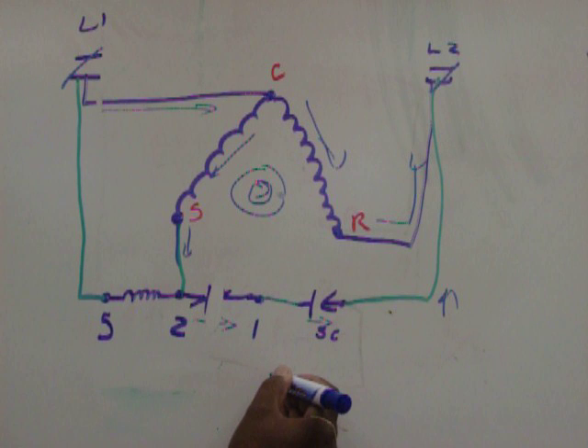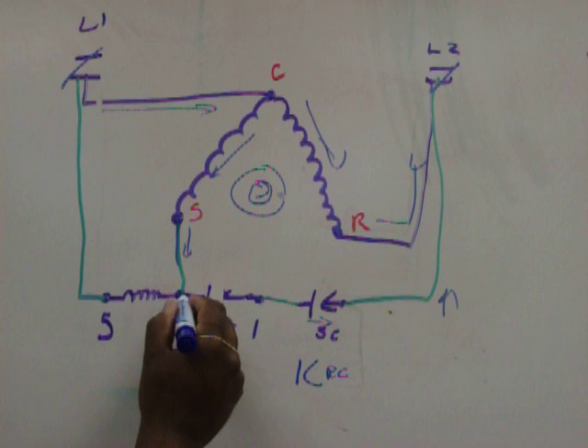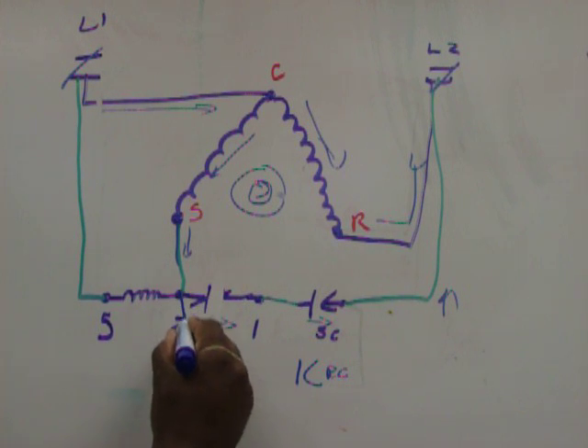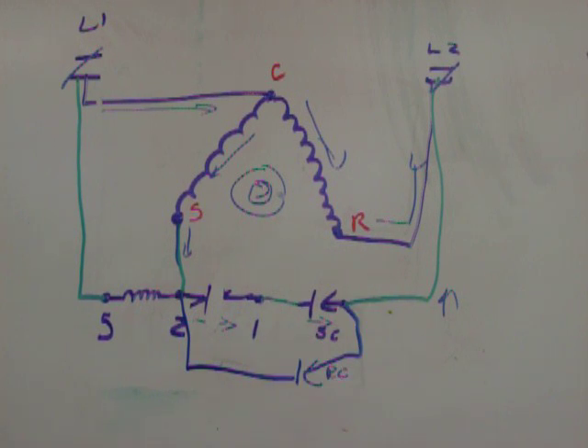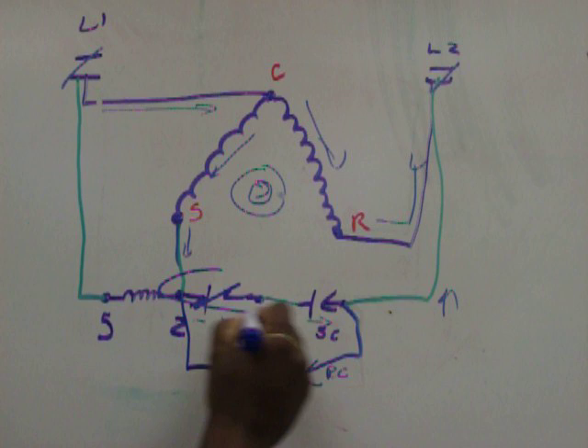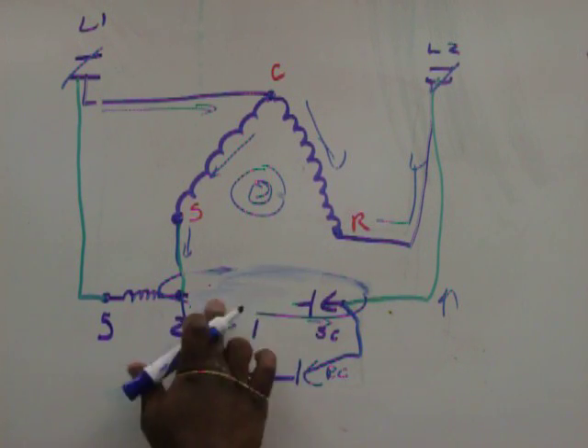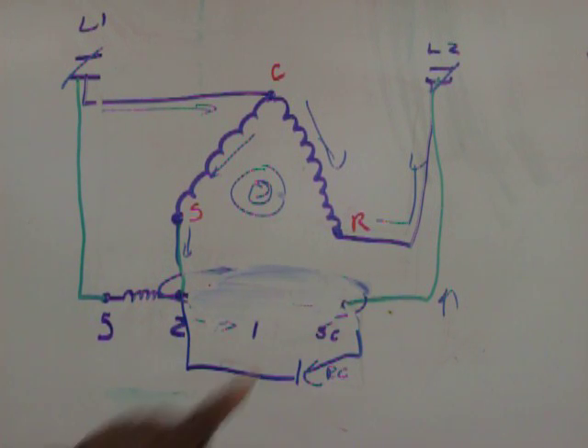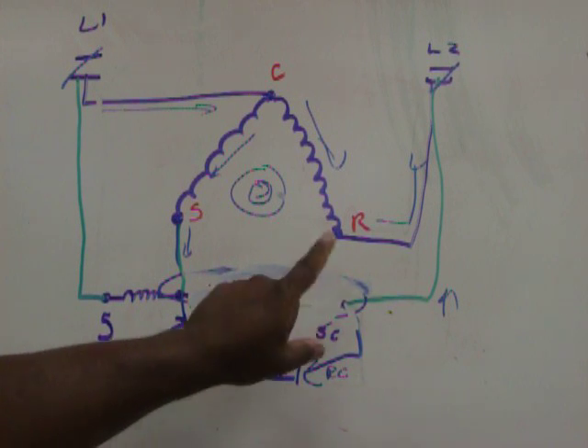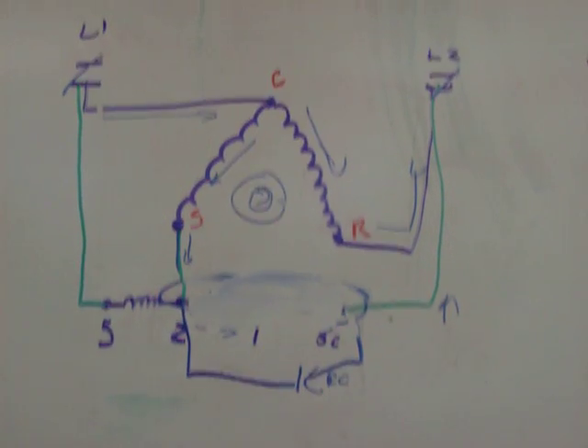Now, you're not going to see them without a run capacitor. So what happens, you just come off of two, go to your run capacitor, run capacitor just ties in here. So what happens on startup, we use this circuit. Once this opens up, this circuit is now irrelevant. Now we're left with a permanent split capacitor motor. We use the start capacitor to start. Once it starts, this kicks it out. And then we use the run capacitor to keep it running. That's what we call a capacitor start, capacitor run motor.